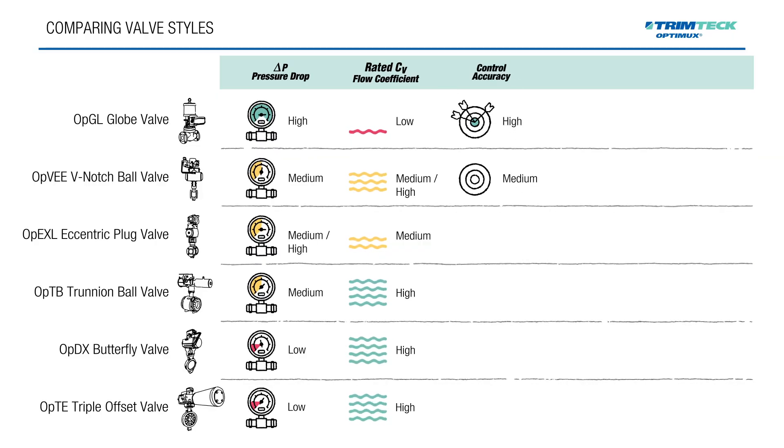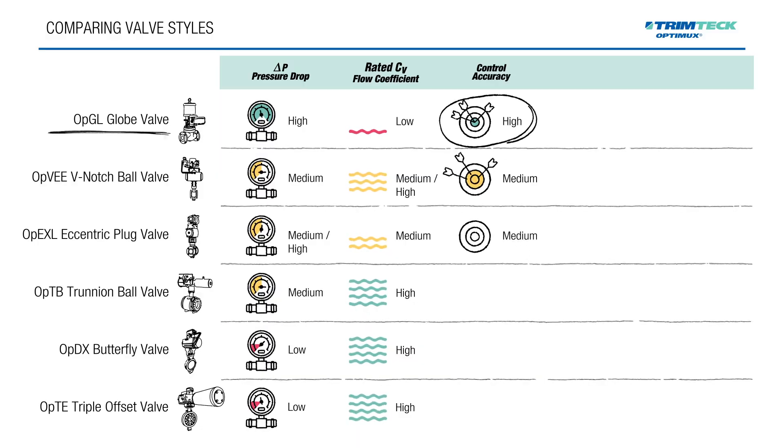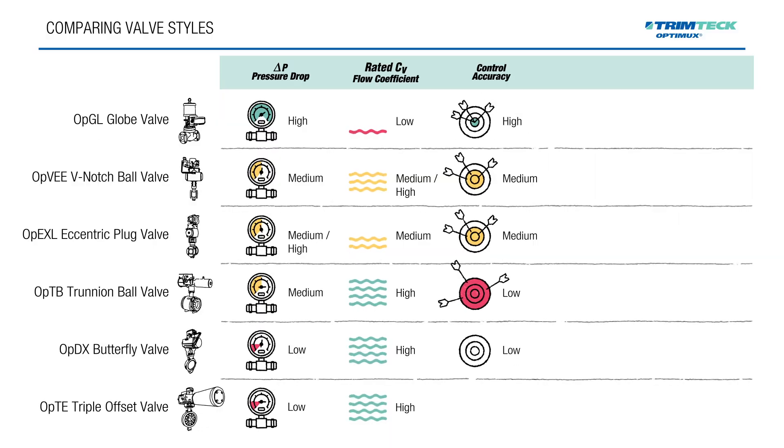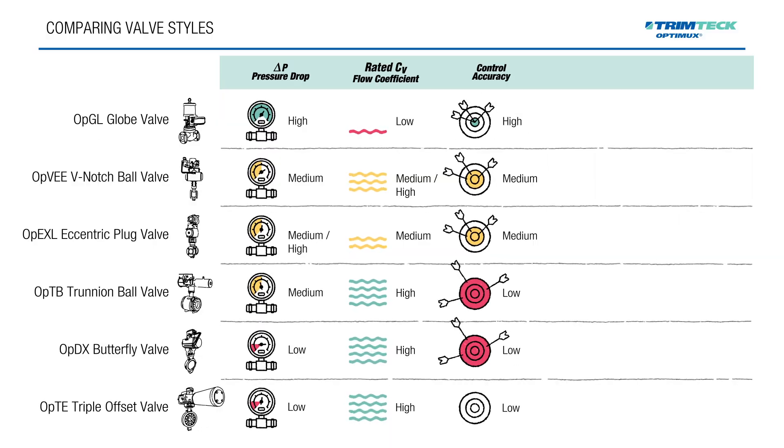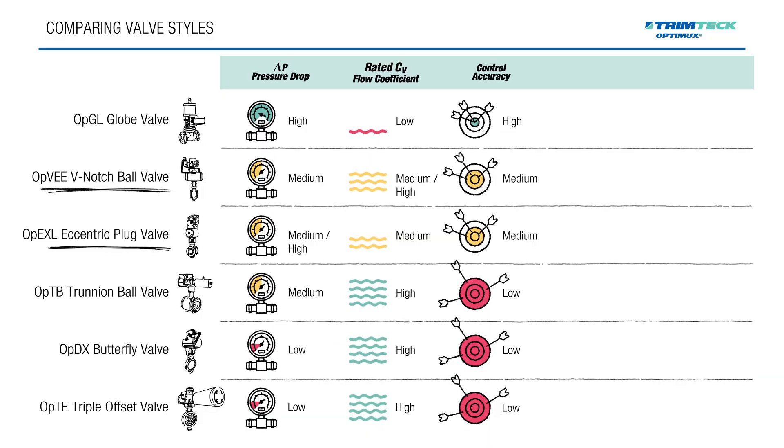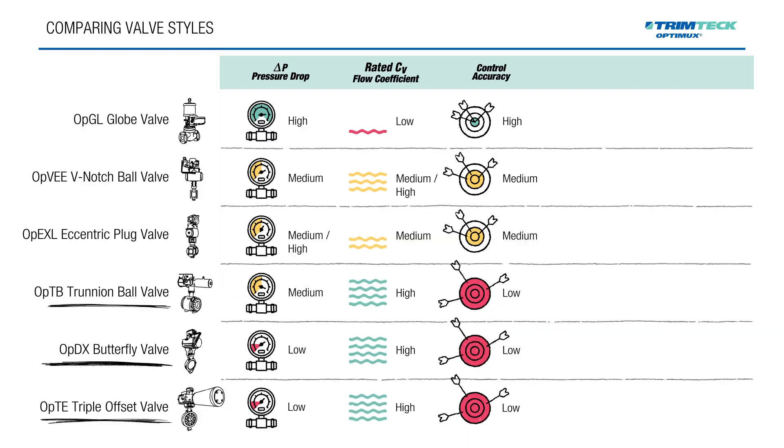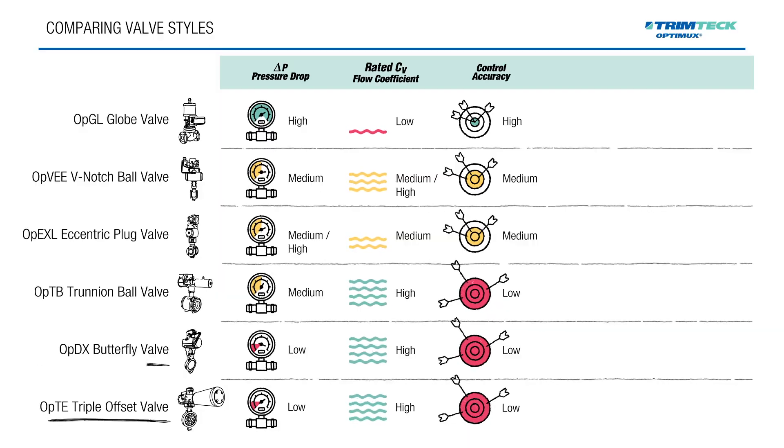Control accuracy is a key factor for many critical applications. Globe valves, especially with custom engineered trims, offer the most precise control thanks to their linear motion and consistent flow characteristics. Rotary valves like V-notch ball and eccentric plug are also accurate, but generally a step behind globes. Trunnion ball and butterfly valves offer less precision, but still work well for many modulating duties.